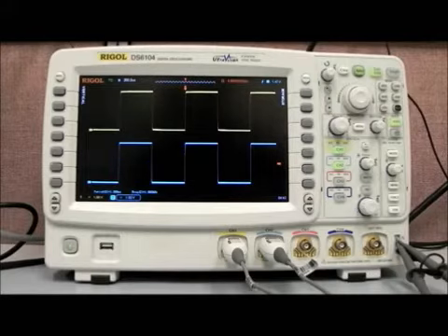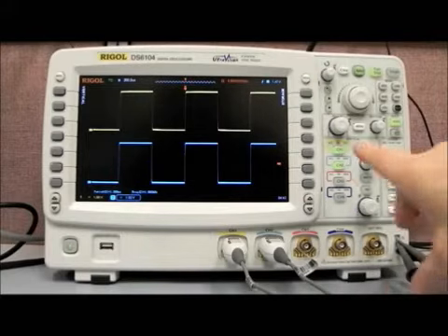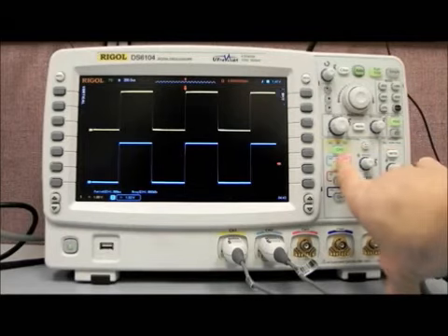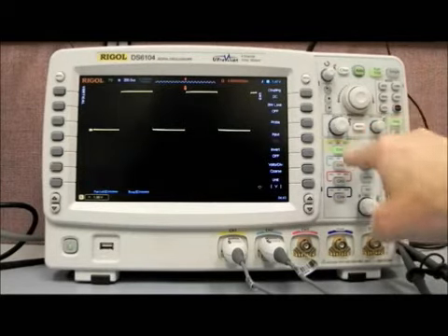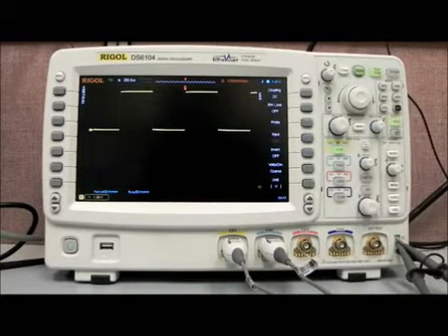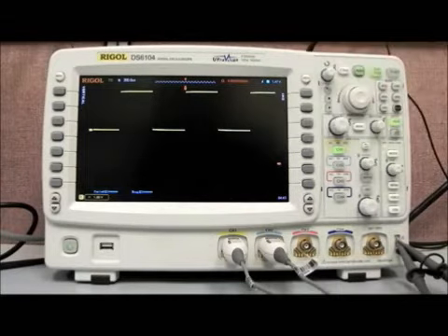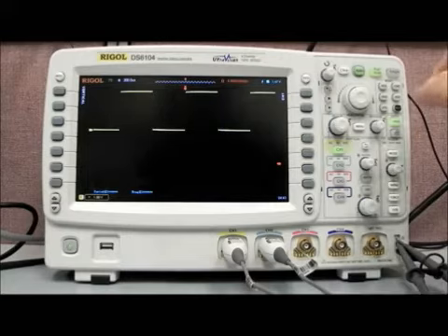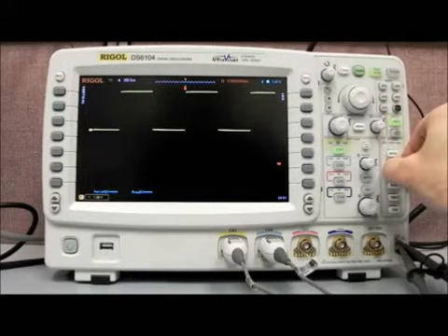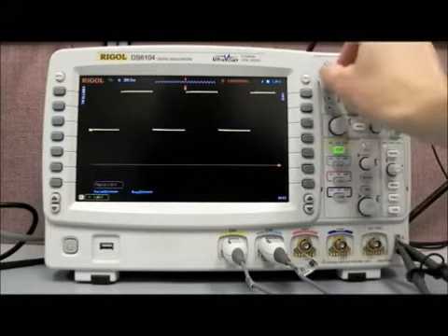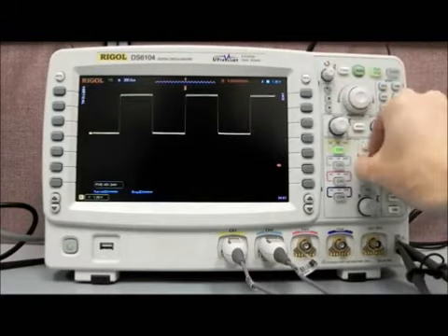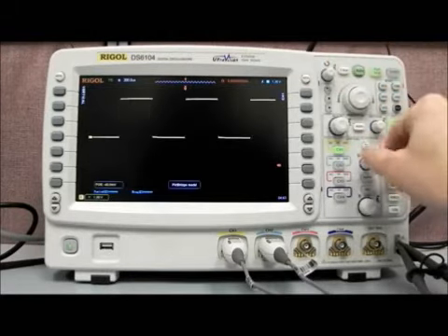So, next what I would like to do, I'm going to disable channel 2 briefly, and we're just going to focus, and again, to disable, we just double press that key. So we're going to focus in on channel 1. To get the menu to slide back, I press the menu key. And I'm going to then bring down channel 1. So I want to select it, and then bring that down using the vertical position.